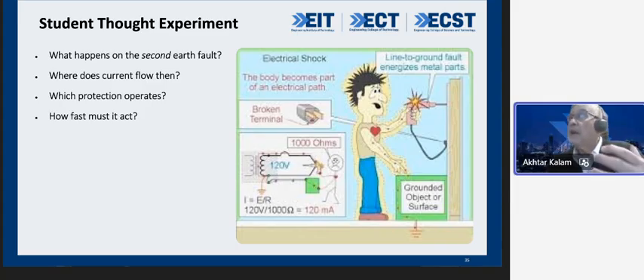What happens if, after the first ground fault, earth fault, a second one came? If it came, there will be insulation failure, there will be short circuit conditions, and there will be system disruption.